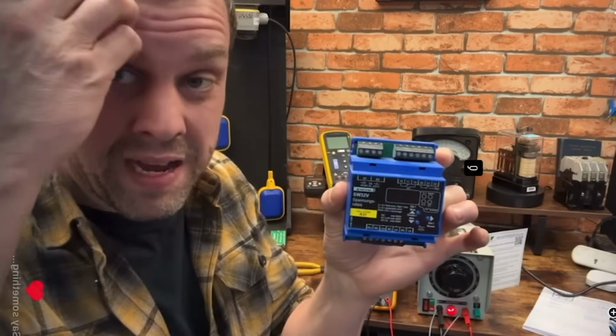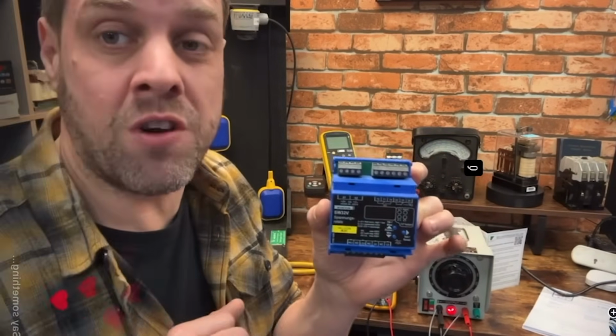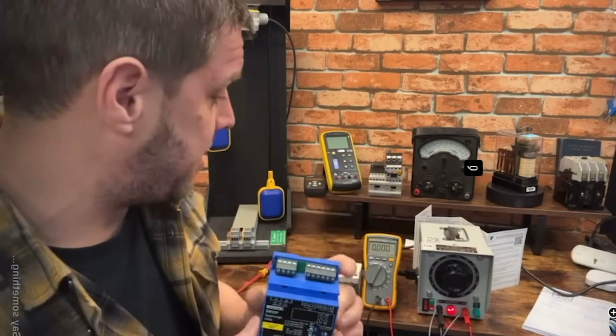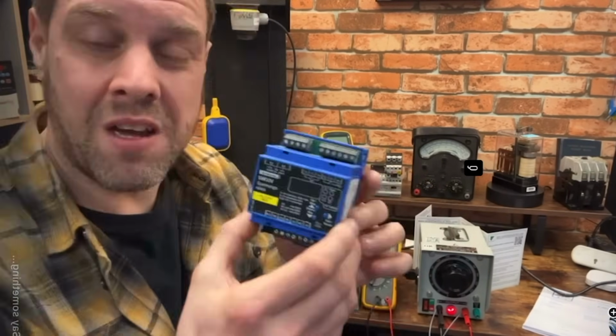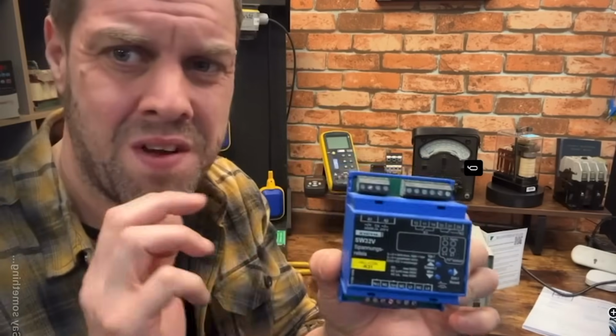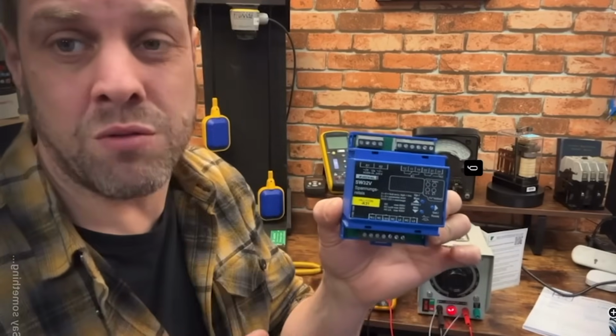So if I'm sending one of these out in a panel and I'm saying it cuts off at 110 and cuts off at 260, I can actually pump that voltage in and check it with my meter. Maybe I'll do a separate video on that, about voltage relays.